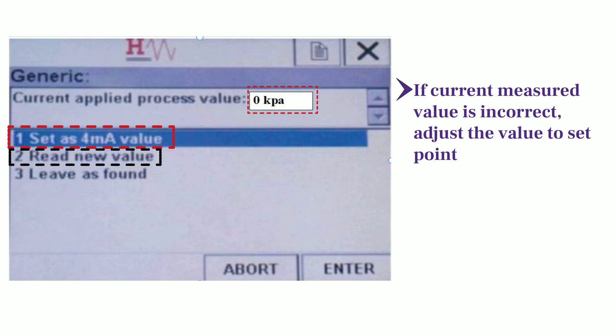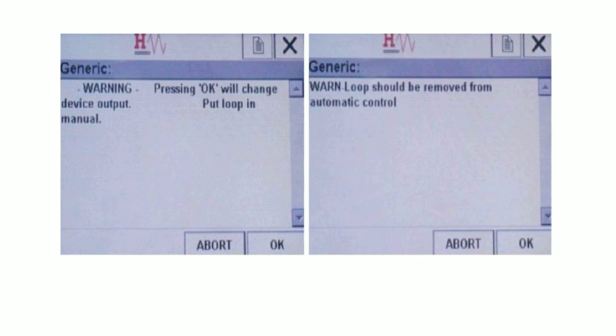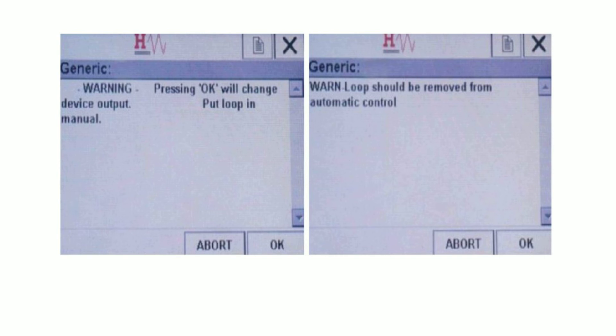In this case, Menu 2 will read the new value from the device. Select Option 1 or 2 and press Enter to confirm your selection. When you set 4 milliampere, it will cause the loop current to change to 4 milliampere. As you can see, changing the calibration values in device may affect the loop current and warning screens like this will appear. Tap the OK to proceed with Calibration Change.